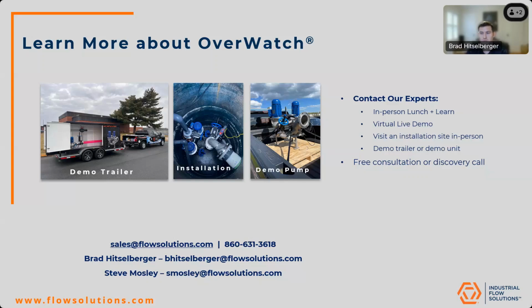Thank you. And then can you share what spare parts are recommended? Yeah, I'll take this one, Brad. One of the common spare parts that we offer with the OverWatch is a completely assembled motor block. That would be everything from the motor down to the impeller. And that allows you to remove the failed motor, install the replacement, and get yourself back up and running, typically within less than an hour. And then you can take the failed motor assembly back to the shop, repair it as time permits, and know that you're running full speed with redundancy in the application.